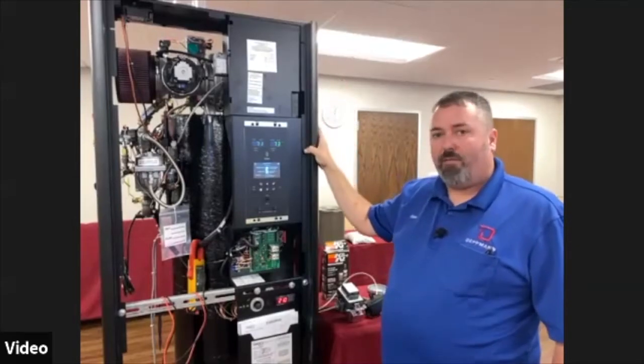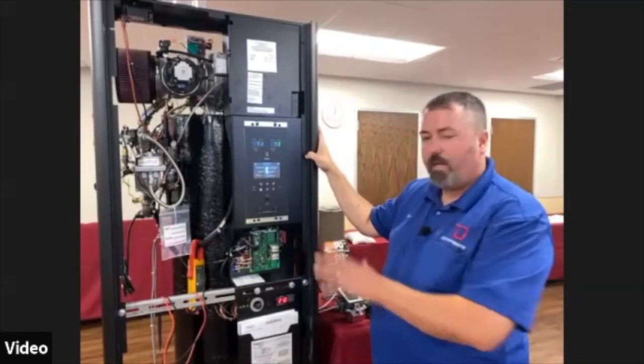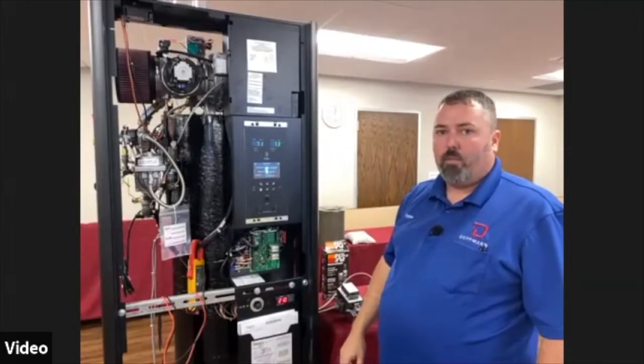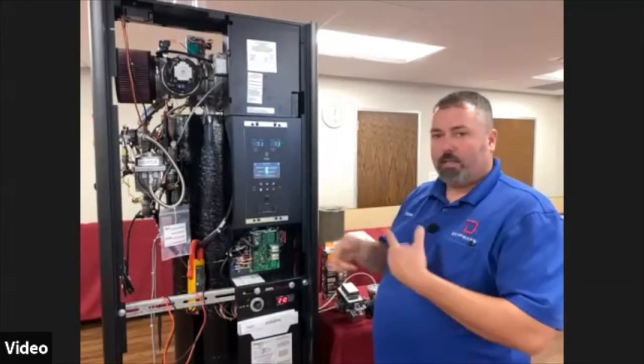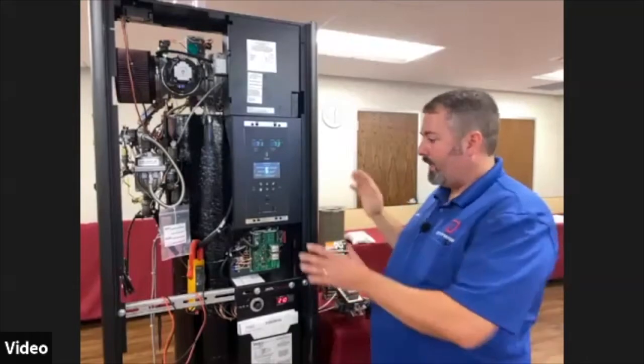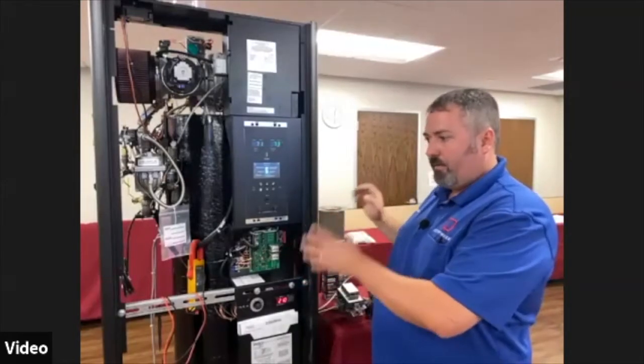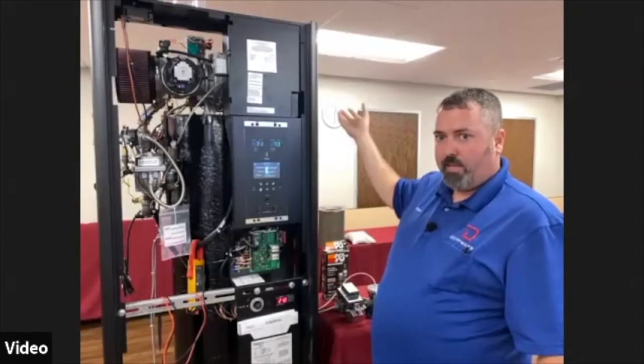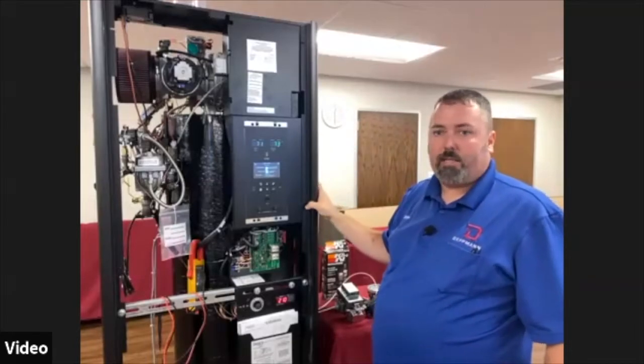They use a standby voltage on these. As long as they're still in standby, it'll send 2 volts to that blower so that it constantly keeps pressure in that flue pipe in case there's several boilers. Just because this one's not running, if the building's in negative, we don't want to suck flue gases in from the stacks that are next to it.